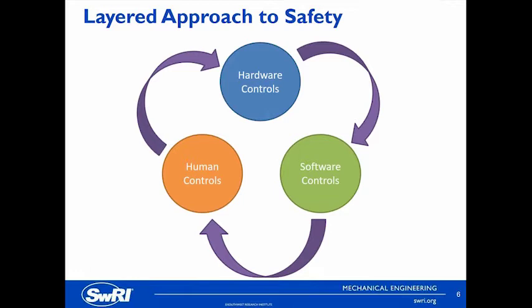Next I will discuss our layered approach to safety. Short of designing your test facility to be made out of components all rated to twice your maximum pressure and operating with 100% automation inside a blast cell, there's really no one task to perform when creating a safe flow facility and testing with pressure. Throughout this presentation, I'll discuss the layered approach to safety where hardware controls, software controls, and human controls work together to create a facility that can be operated safely while still being economical and practical.